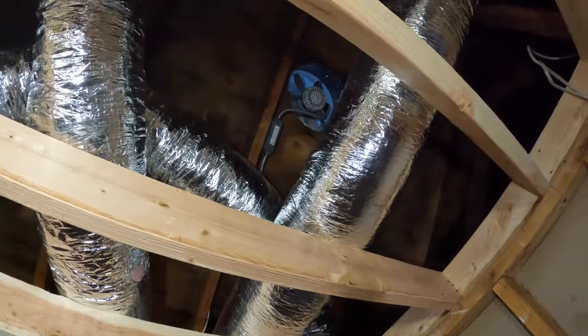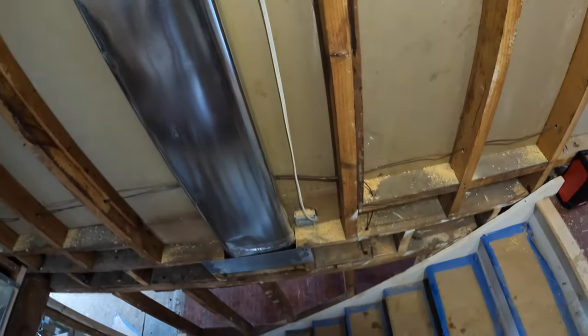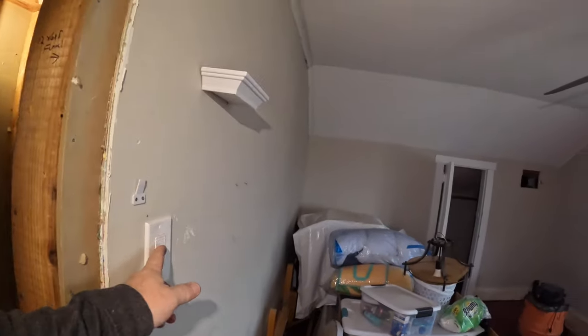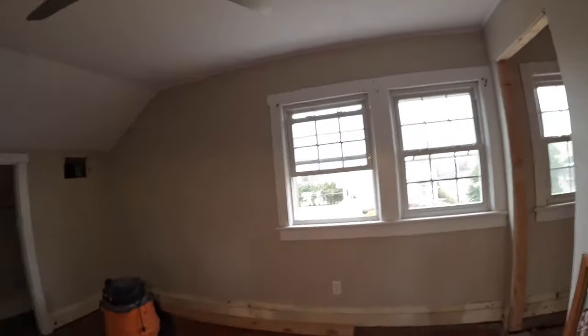So one has to be - looks like it's supplying the exhaust fan. That's a disconnect switch and an exhaust fan. And the second one actually comes down here for that receptacle, so we're going to resupply that. And then we have to resupply this circuit as well for this bedroom, which has this light switch and the ceiling fan. This receptacle on the exterior wall used to be a piece of PVC - a PVC home run that went down the siding, all the way down. But since we raised this house and we're doing all this work, let's get rid of that PVC and do it right.